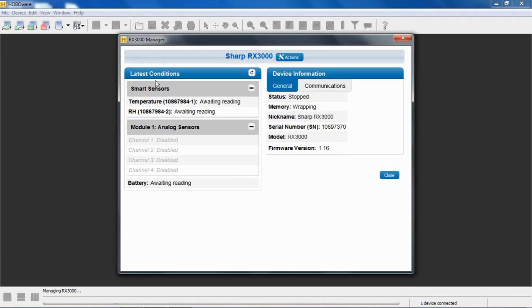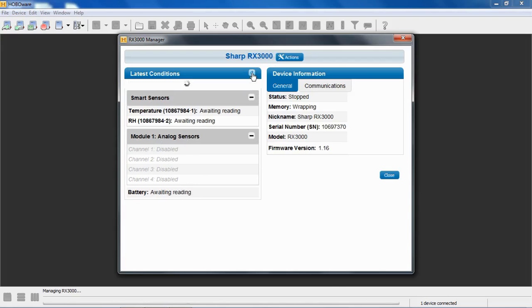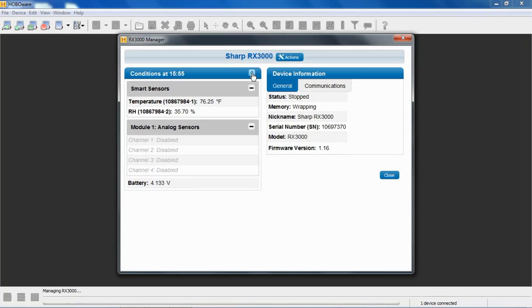So it has two halves to the page. Latest conditions, where we can see the status of the sensors and the battery. This particular device has a temperature and relative humidity sensor attached. It has a four channel analog module with channels that are not configured, and we can check the battery level. To refresh these, there's a refresh button right here. We can press and it goes out and scans the bus and populates these with the current conditions that it sees. So there's our temperature, our relative humidity, and our battery level.